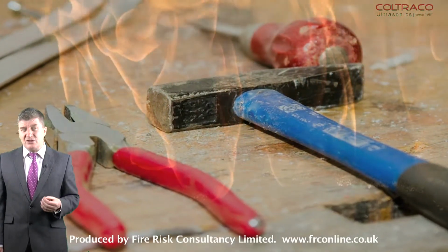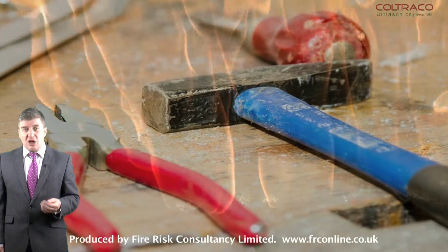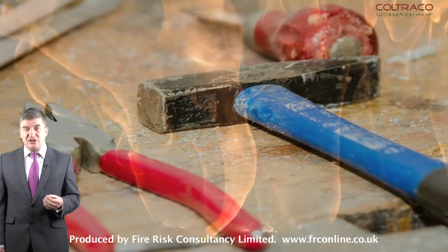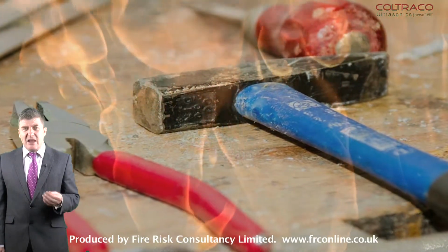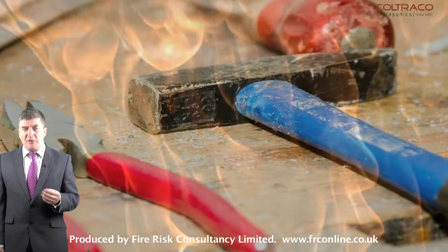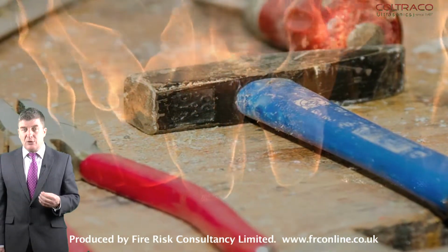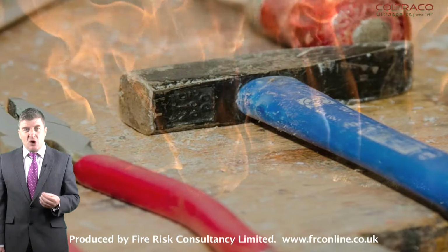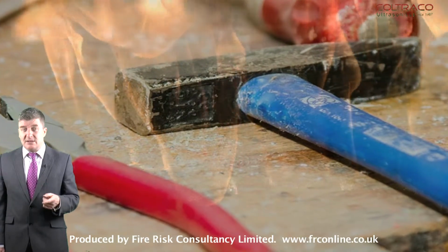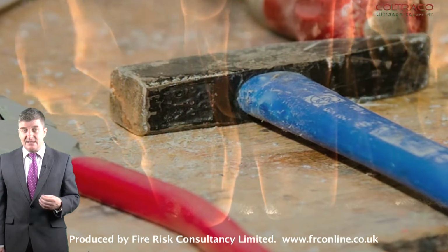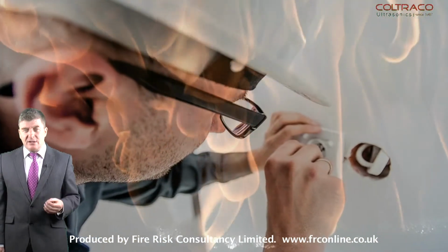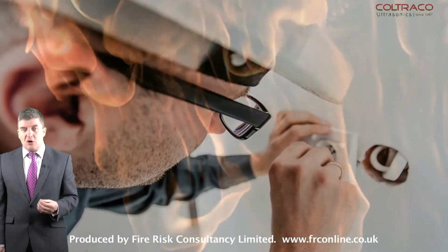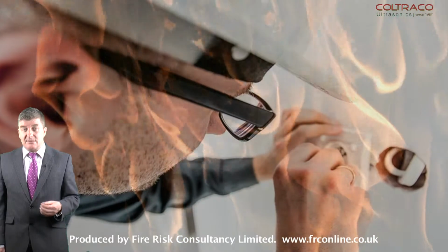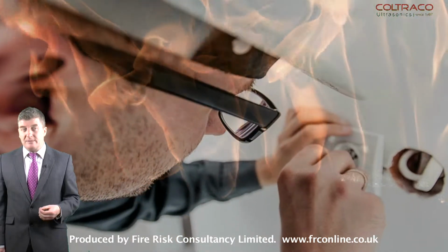Maintenance, what is that definition? Well, it means a thorough check comprising a thorough examination and any necessary repair, adjustment or replacement of system components to give maximum assurance that the extinguishing system will operate as intended. Inspection, this is to give reasonable assurance that the extinguishing system is fully charged and operable.